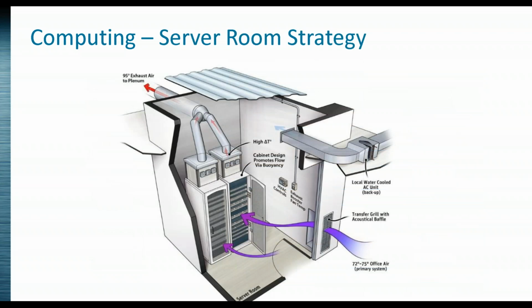But when you get into bigger computing, we've seen almost a hot aisle, cold aisle strategy even for small server rooms with a server closet. Instead of having the fan coil mix the heat off the unit into the room, we capture it off the top, send it to the fan coil unit, and bring air in. So we don't water down the cooling provided to the space—let it be as effective as possible going in the front of the rack, coming out the top or back, and being taken away.